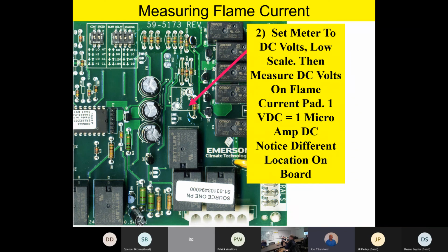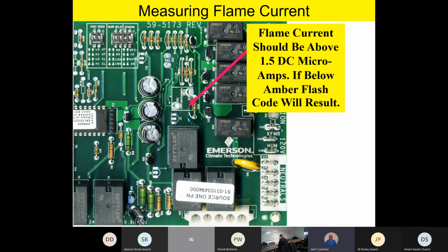Now remember, team, 1 volt DC is equal to 1 microamp flame current. And again, please remember and notice the difference of where the location of that flame current pad is on the board. It's in a little different spot on this board. And so 1 volt DC is 1 microamp flame current on the board. Now it should be noted, if the flame current falls below 1.5, you're going to get an amber flash code on our little LED that's telling us we have low flame current.